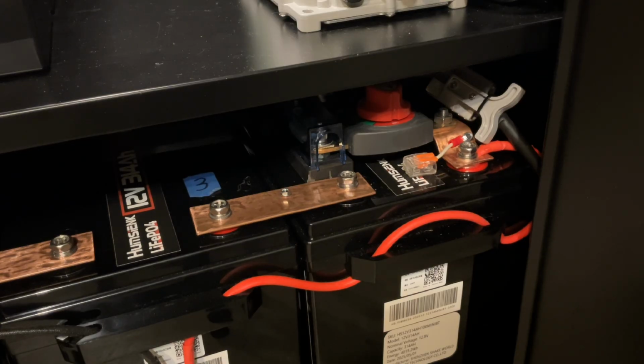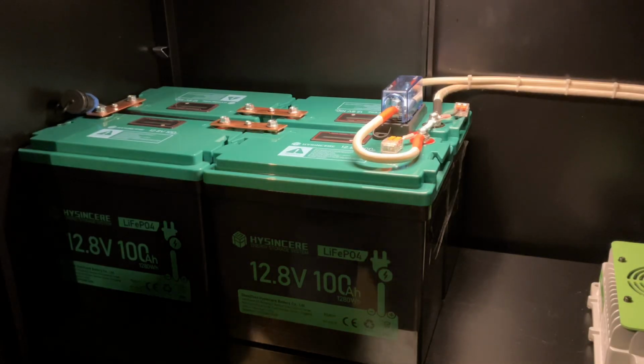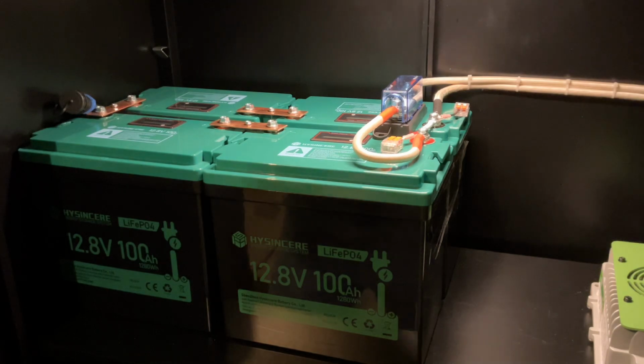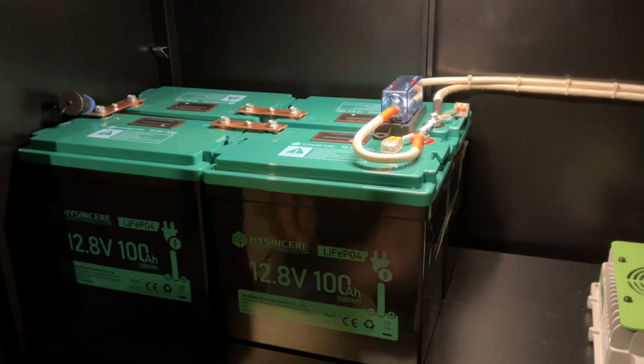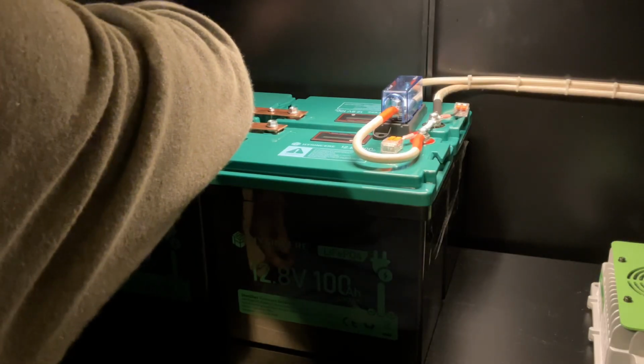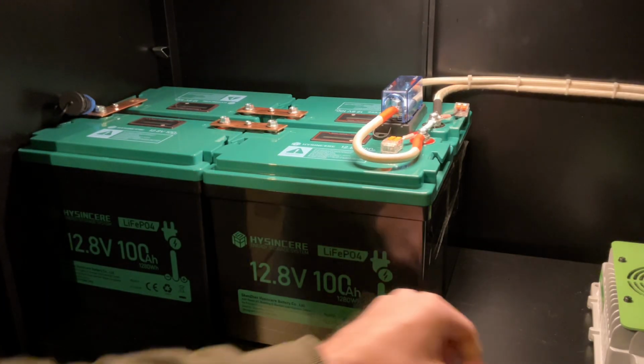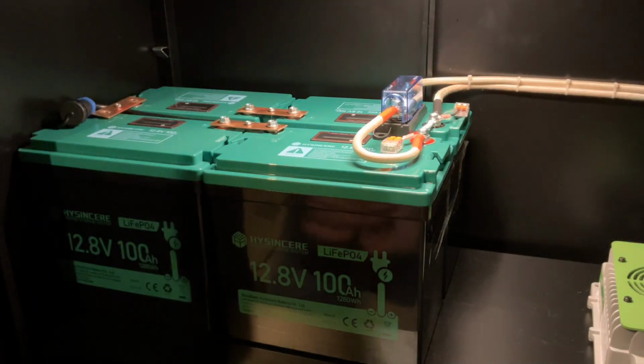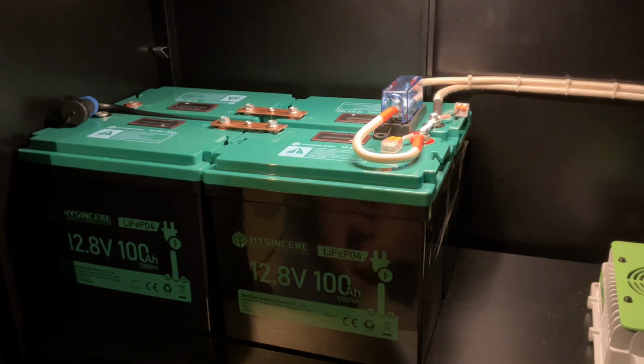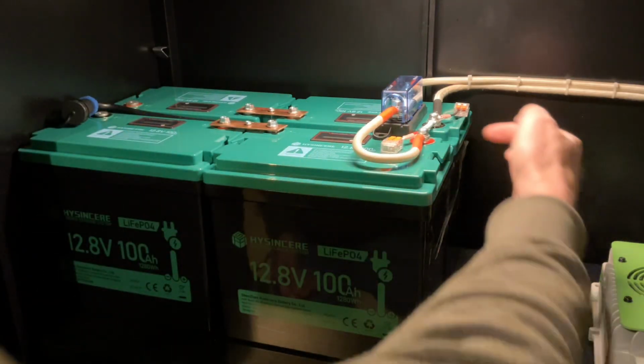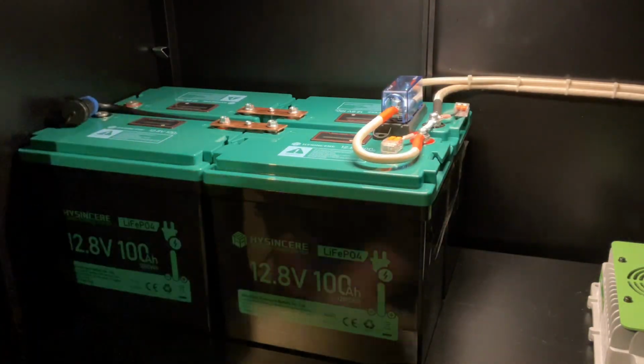Now I'm going to disconnect the wiring from the Hysincere battery bank. I'm going to remove the bus bar from the middle of the battery pack, which will separate the pack voltage in half. Removing the bus bar from the middle of that pack opens the electrical connection, so there is now no electrical connection between these posts anymore. I've opened that connection on the battery, and I'm going to go ahead and disconnect the main positive and negative off of the battery.